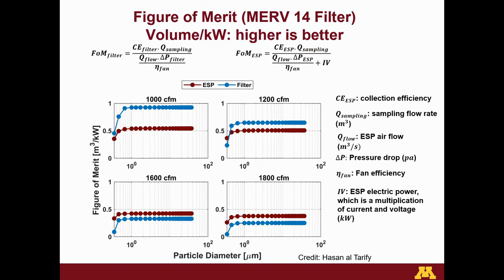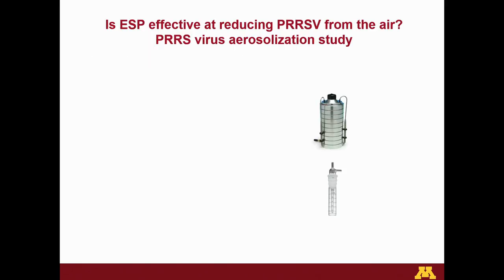So what it is, I'll spare you the details and the equation, but it's looking at the collection efficiency, the flow rate, the pressure drop, and the fan efficiency. And the one difference there is we have to add back in to the ESP the energy used to operate the ESP, right? So a fair amount of noise there, but at the higher pressure it would indicate a better figure of merit for the ESP over the filter, and the opposite in the lower, which makes sense as you're using energy to run the ESP unit and have very low static pressure at that time due to lower flow rates.